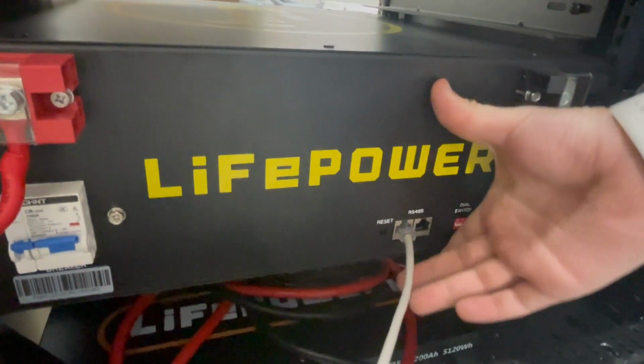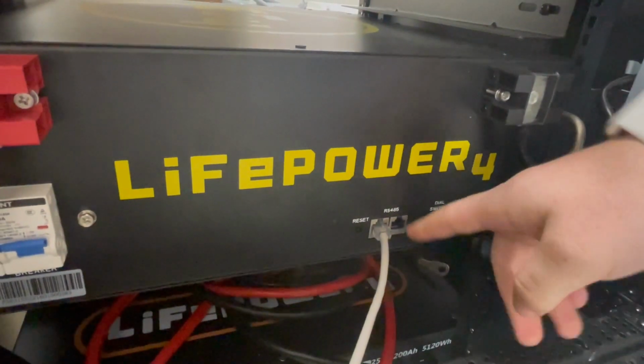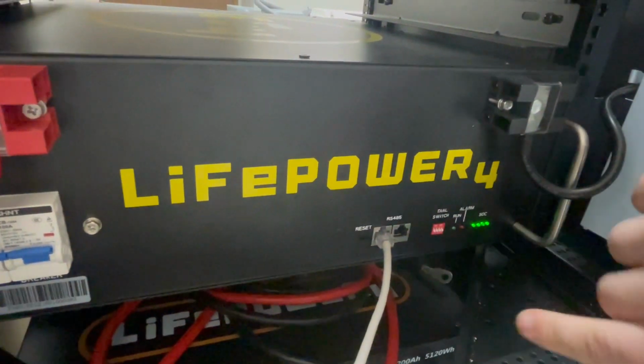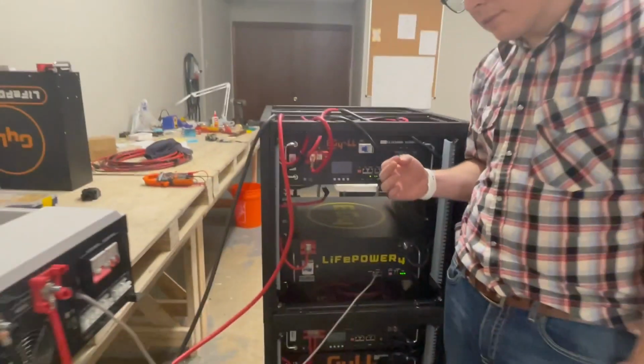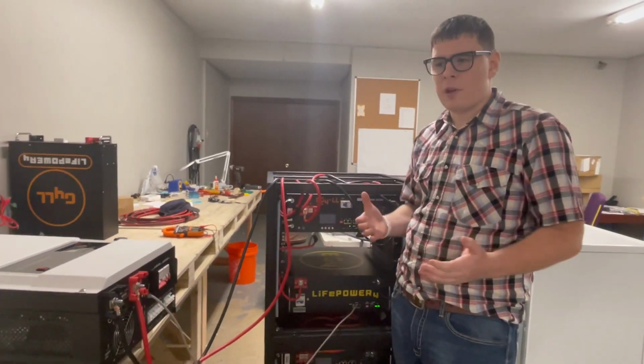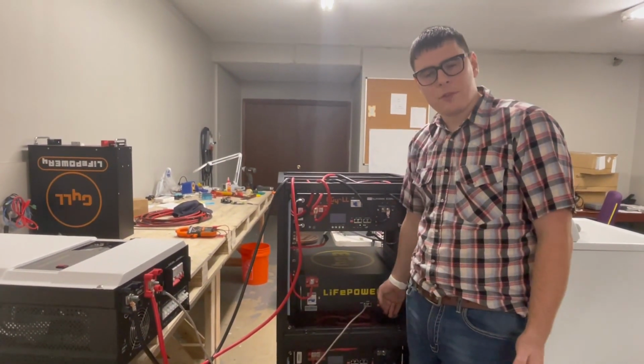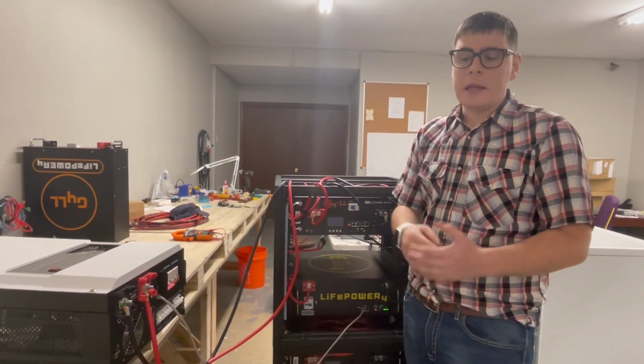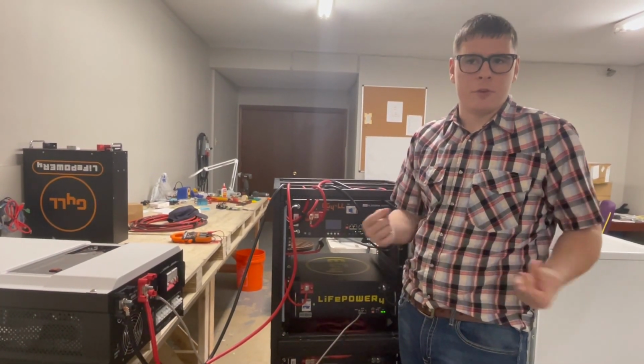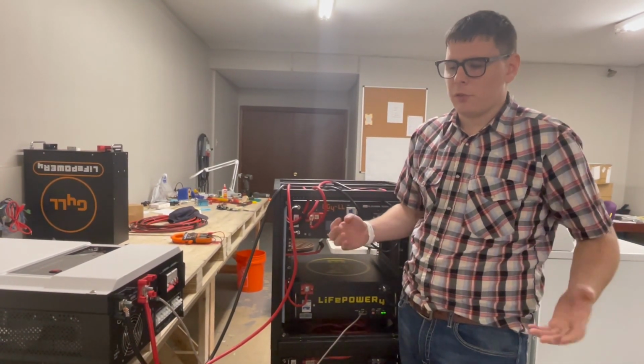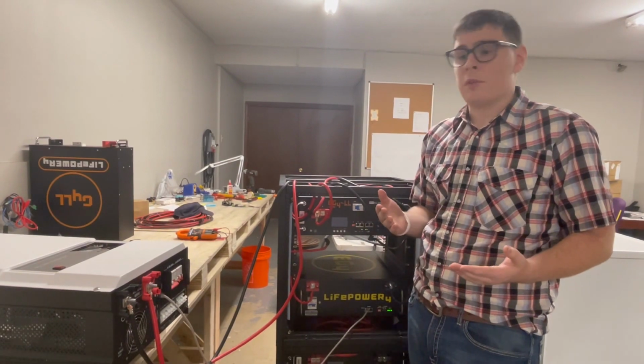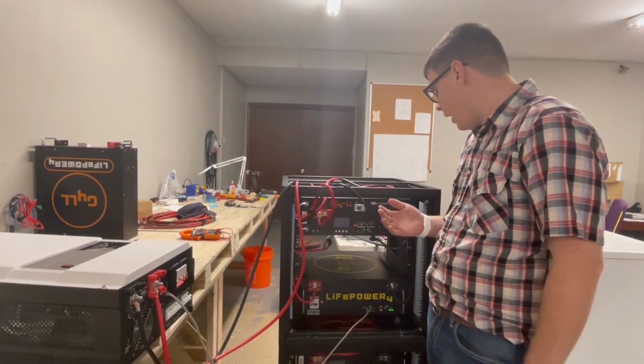Now if you had multiple batteries, they would just be daisy chaining from this extra port to the next battery. And the main thing you have to keep in mind with that as well is that no other battery should have an address conflict. So this one is address zero, all four switches down. Any other batteries need to have different addresses on them. You never want address conflicts.